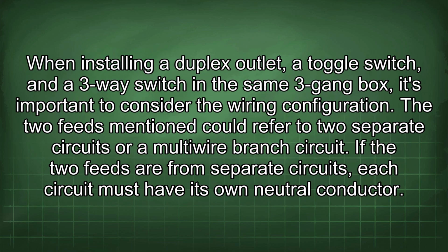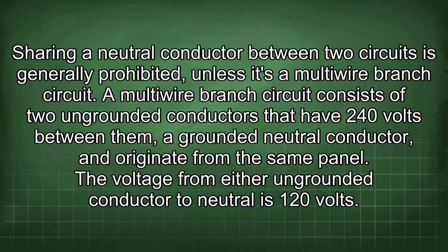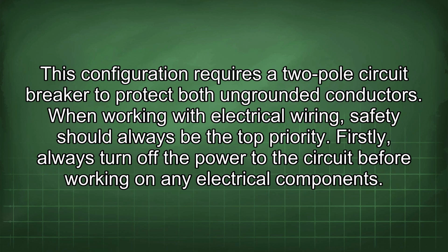When installing a duplex outlet, the toggle switch, and a three-way switch in the same 3-gang box, it's important to consider the wiring configuration. The two feeds mentioned could refer to two separate circuits or a multi-wire branch circuit. If the two feeds are from separate circuits, each circuit must have its own neutral conductor. Sharing a neutral conductor between two circuits is generally prohibited, unless it's a multi-wire branch circuit. A multi-wire branch circuit consists of two ungrounded conductors that have 240 volts between them, a grounded neutral conductor, and originate from the same panel. The voltage from either ungrounded conductor to neutral is 120 volts. This configuration requires a two-pole circuit breaker to protect both ungrounded conductors.